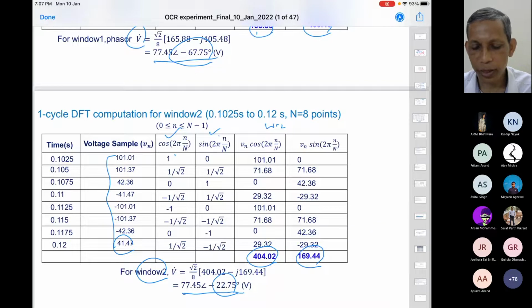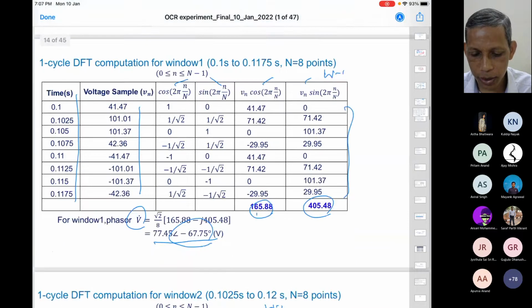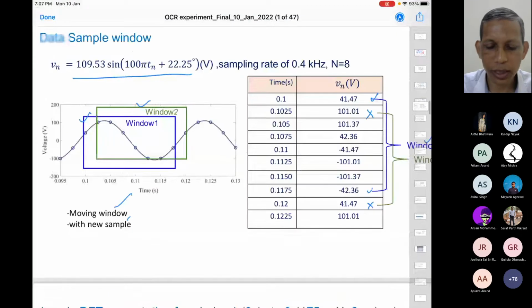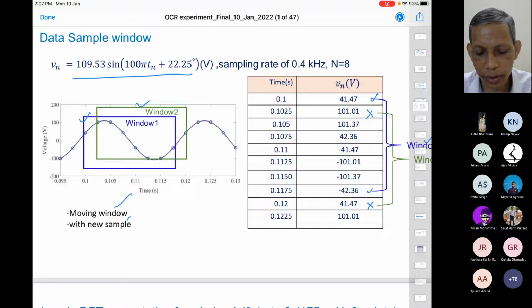Ready? The magnitude remains the same. Why does it remain the same? If you see, this signal is nothing but a steady state signal. No fault, nothing. So what will happen here? Same window, same RMS value will be there, fundamental component, peak divided by root 2. That's why you are getting 77.5, this 109.53 divided by root 2, the RMS value. Agree? And the other point is that window 2 has shifted forward by 45 degrees.